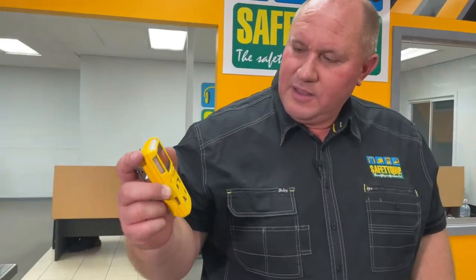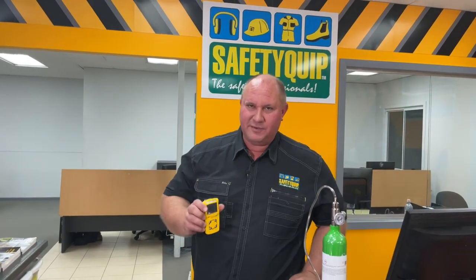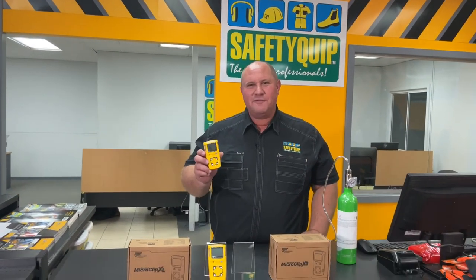That will go back to normal levels fairly quickly and it's just about there now. That's good to go. On this one, the green light flashes on the top when it's good to go. If they'd stabilised at what was on the cylinder, I'd be satisfied to use that gas detector and start work. Speak with the team at your local SafetyQuip branch regarding your particular scenario of gas detection — we'd love to help out.